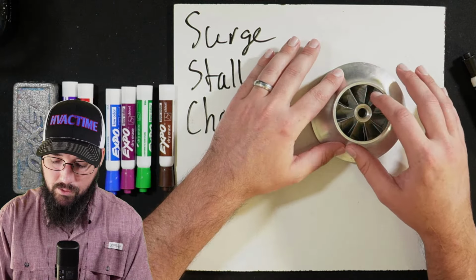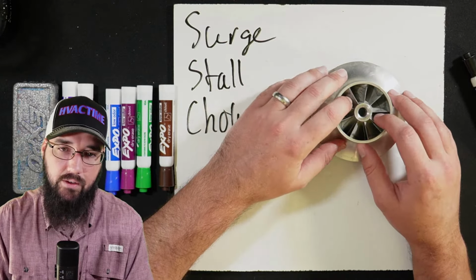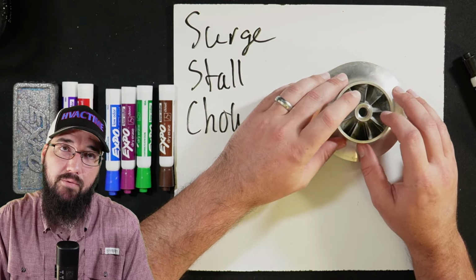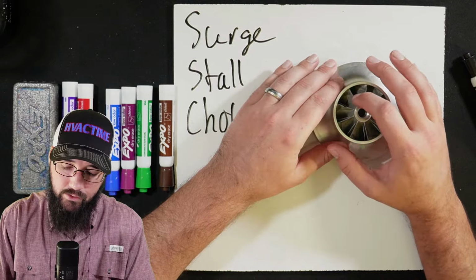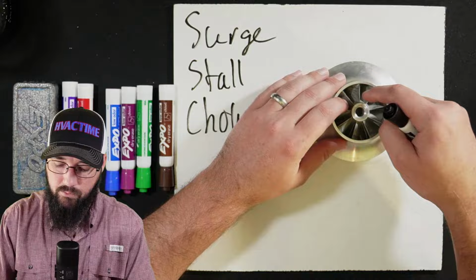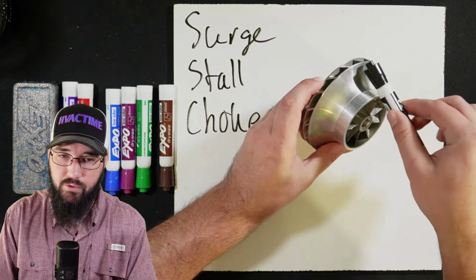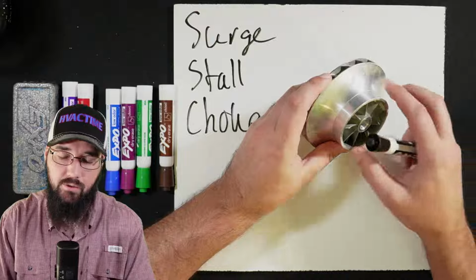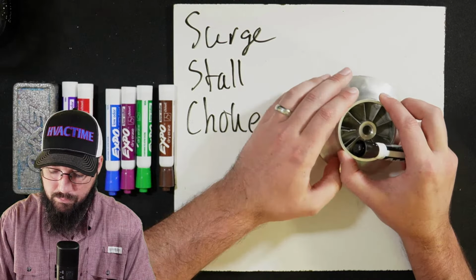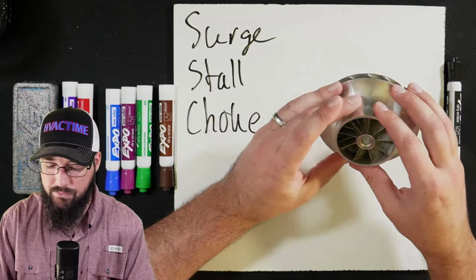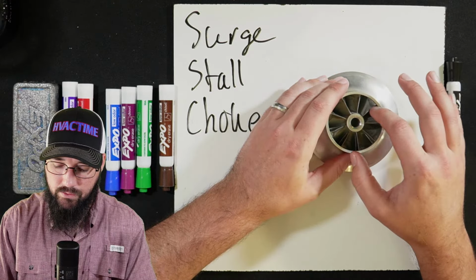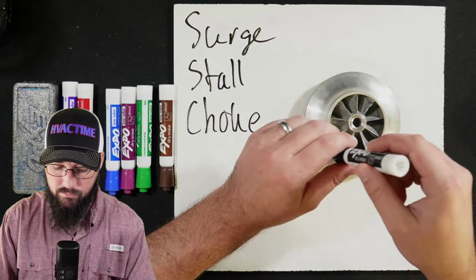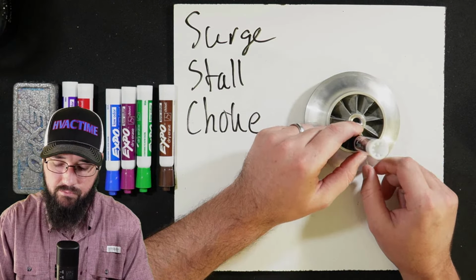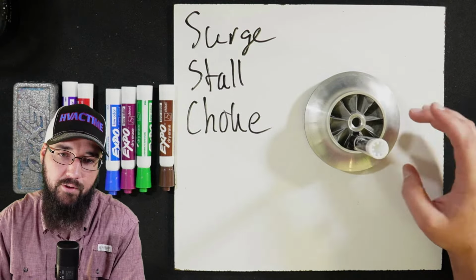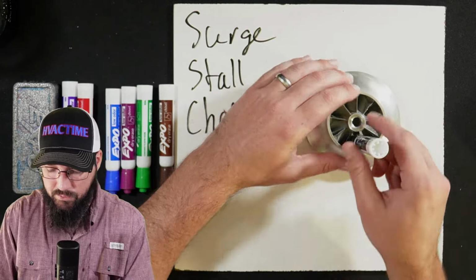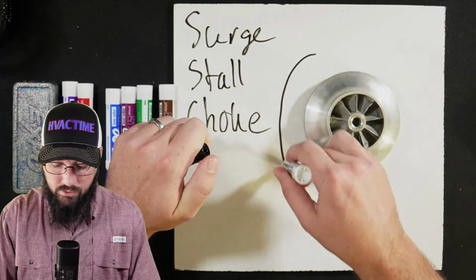we'll get into a spot where some of these vanes will stop flowing refrigerant through them. Okay, so quite literally, refrigerant is flowing through most of these others, and it's being sent out into the compressor. But then we'll have some of these that won't be, right? So we'll use this one as an example. This particular vane of the impeller stopped moving refrigerant while it's rotating.